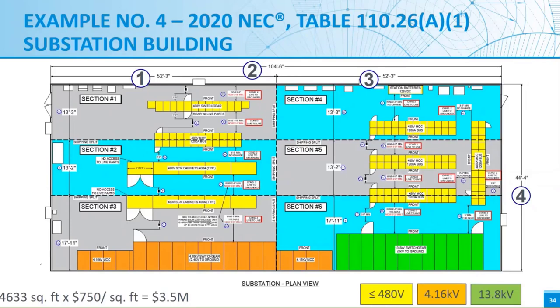slides, I'm going to zoom into each section and we're going to take a closer look at the delta and dimensions from the minimum working space dimensions between the 2017 and what is required now by the 2020 revision. The equipment is identical. We've not added or taken away anything. And they're in the same positions right now that we just saw on the previous slide. But one of the first things that becomes pretty obvious is the growth in the dimensions shown near bubble four to the far right, which is now 44 foot 4 inches, whereas before it was only 40 foot 7 inches. Dimensions 1, 2, and 3 remain the same for this example.